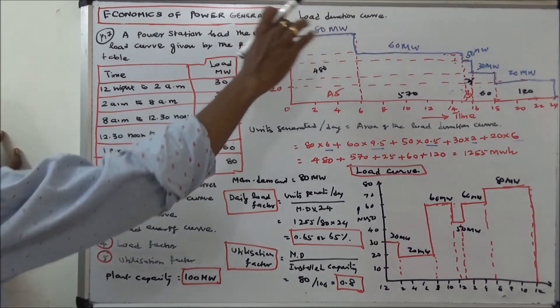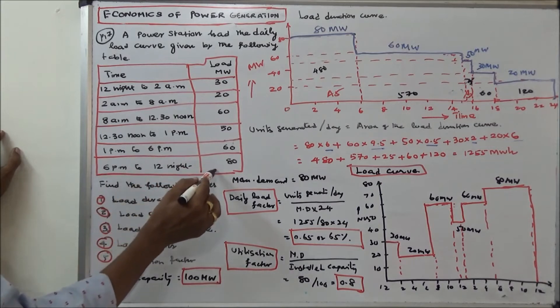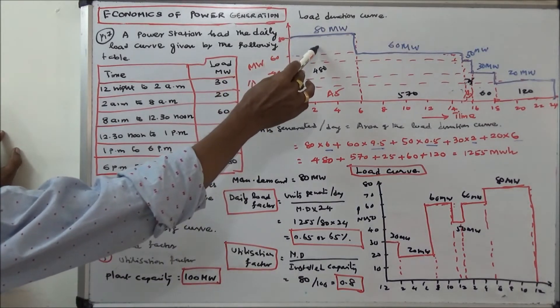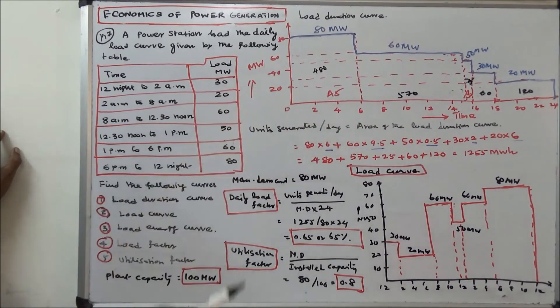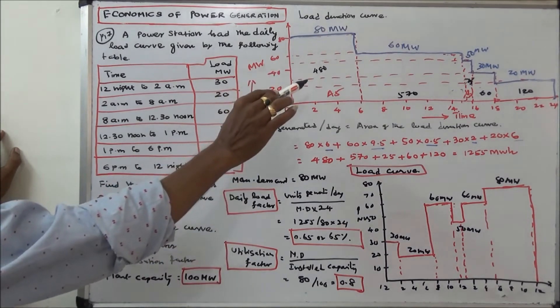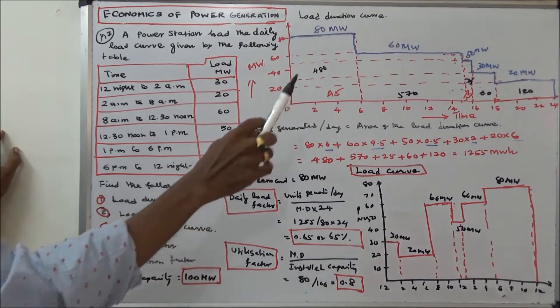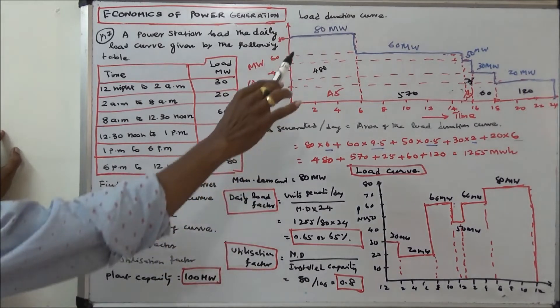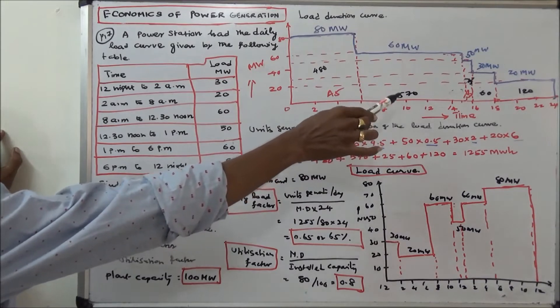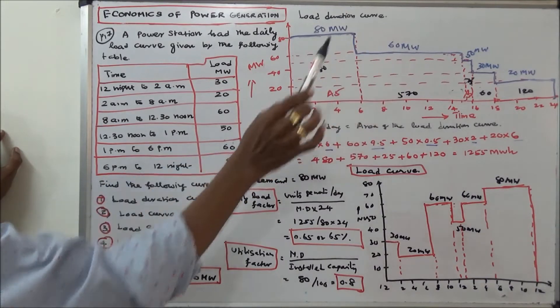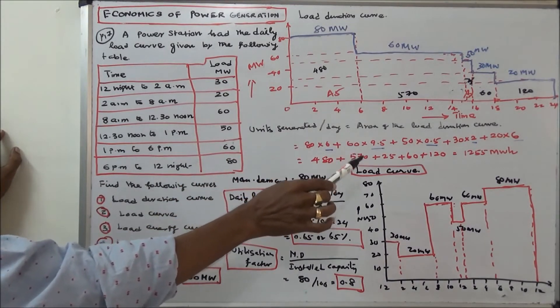First, draw the load duration curve. From 6 PM to 12 night, the load is 80 megawatts. Next is 60 megawatts, 50, 30, and 20. From the load duration curve, we can easily calculate units generated per day — that is equal to the area of the load duration curve. Area equals 80×6 + 60×9.5 + 50×0.5 + 30×2 + 20×6. So units generated per day equals 1255 megawatt hours.